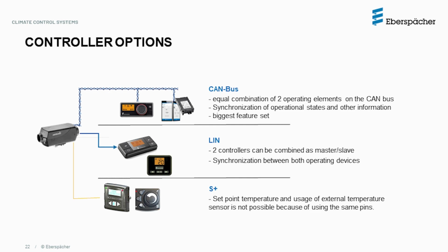The Airtronic 2 heater can be operated with more than one controller and with different controller types. However, in this kind of a setup, some controller types will have a higher priority over others. For example, a CAN-based Easy Start Pro controller will have higher priority over a LIN-based Easy Start Timer, and likewise, the Easy Start Timer will have higher priority over the analog Digimax controller.